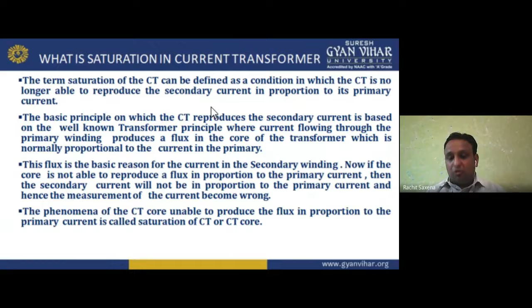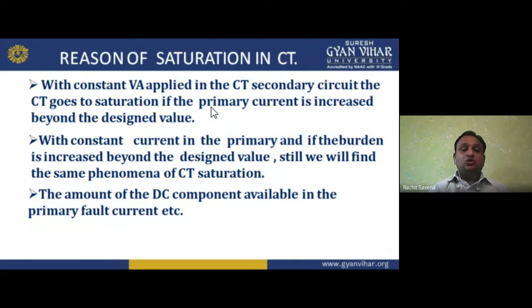The causes of saturation in a CT are as follows. With constant VA applied in the CT secondary circuit, the CT goes into saturation if the primary current is increased beyond the desired value. With constant current in the primary, if the burden is increased beyond the desired value, we find the same phenomenon of CT saturation. Also, there is the amount of DC component available in the primary fault current, etc. So these are the reasons why we have saturation in a CT.